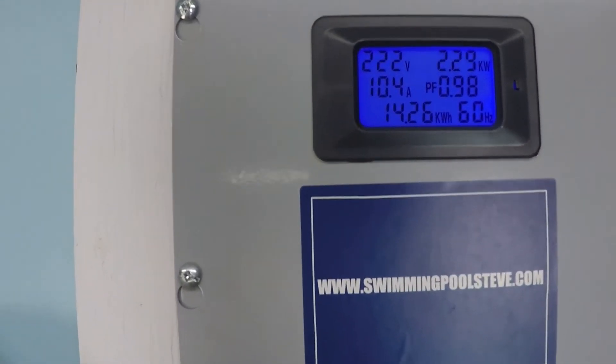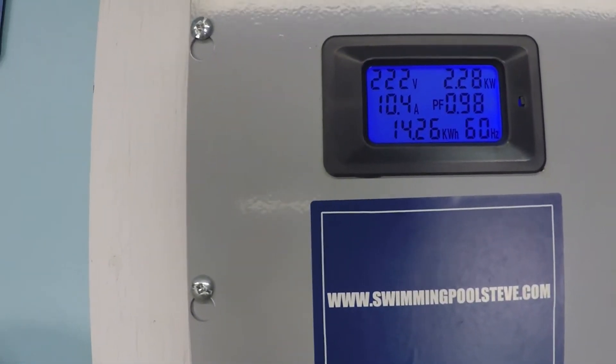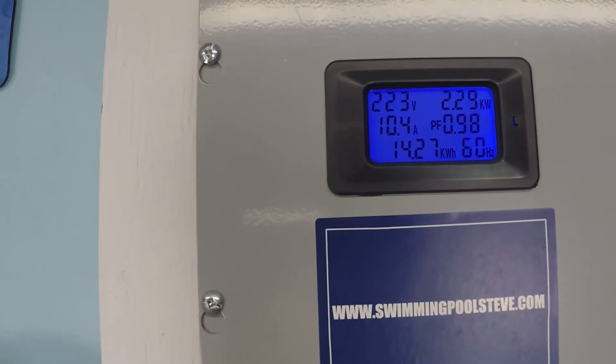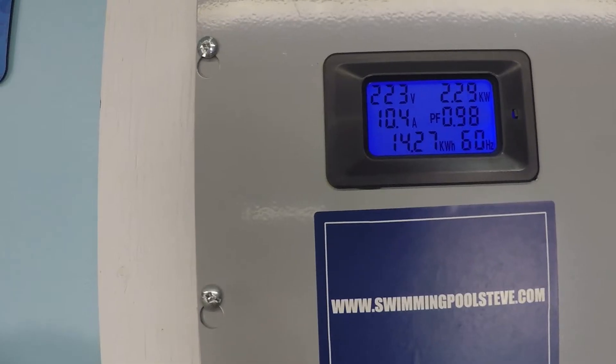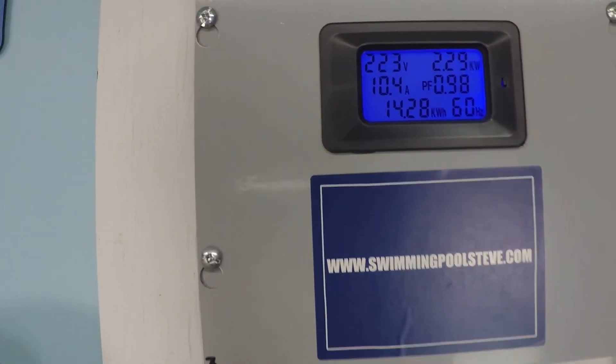So just over 100 gallons per minute. Power consumption 2.29 kilowatts. That's 2,290 watts. Just over 10 amps of current draw.